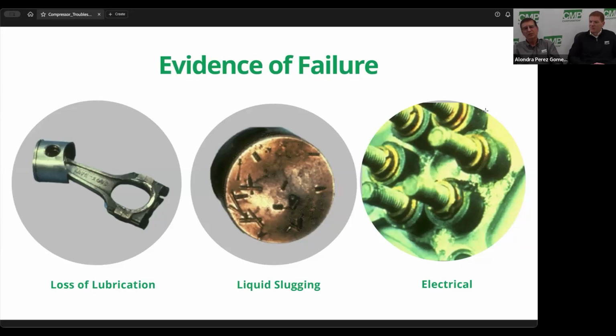And make your own. There are two things you need to make. Maybe make up your own startup sheet for when you have a compressor failure. It'll make you check things that you normally would forget or wouldn't check. Okay, this is good. So how can we help people? What should be on this compressor startup sheet? I'm sure you guys have tons of them that you send out to all your customers. But if I'm a technician and I'm going to go out there and build my own, they're listening right now, I'm going to a site right now, what should be on that compressor checklist?